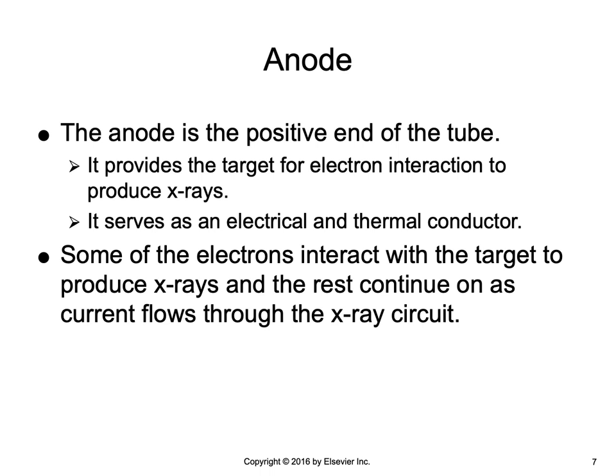The anode is the positive end of the tube and it provides the target for the electron interaction to produce x-ray photons; it is an electrical and thermal conductor. Electricity flows through the x-ray tube, and the electrons flowing from cathode to anode are part of that flow. Some electrons interact with the target to produce x-rays, and then the rest continue as current flow through the x-ray circuit. A tremendous amount of heat is also generated during the process, and the anode is designed to dissipate this heat.